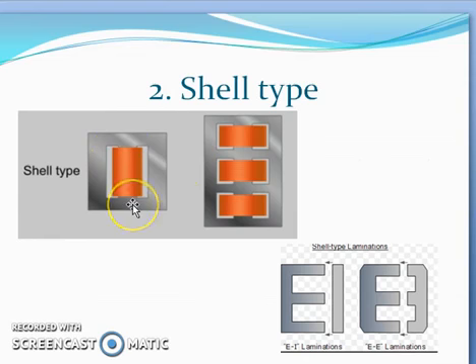The width of the central limb is double that of the outer limb. Mechanical strength of shell type transformers is high compared to core type transformers, and losses are less compared to core type.